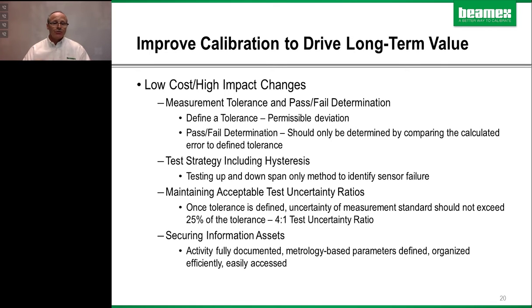Second is a test strategy including hysteresis. Hysteresis is the difference between a response to an increasing input versus a decreasing input. A lot of our test strategies, 0% and 100%, are absolutely terrible. It's almost useless. 0%, 50%, and 100% on the scale is a good balance between practicality and feasibility. But if you go up the scale and back down, hysteresis is going to show you if there's a difference between increasing and decreasing inputs. It is a friction on a sensor somewhere, and that says that instrument is about to fail. It needs to be corrected or replaced. You'll never find it without hysteresis.